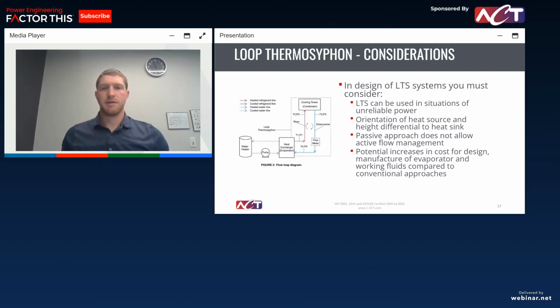And then also compared to a single phase solution, you'll typically have an increase in costs of design or manufacture as upfront costs, just because oftentimes these brazed internal geometry evaporators can be a little more expensive than your standard cold plates. But the one advantage is you don't have nearly as much in terms of active cost. Running the system is going to cost you a lot less because there's a lot less maintenance and there's a lot less power draw.